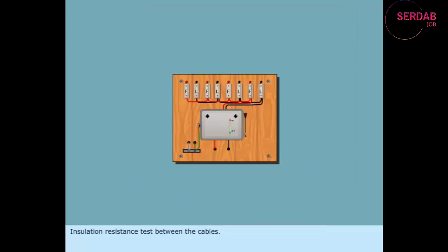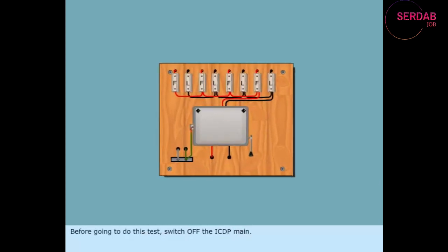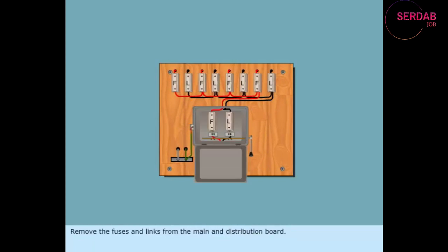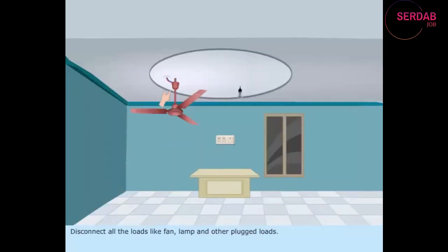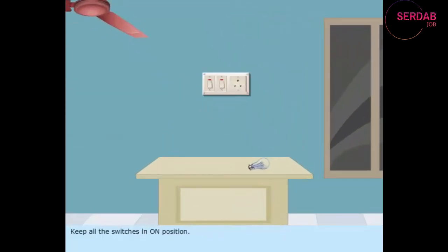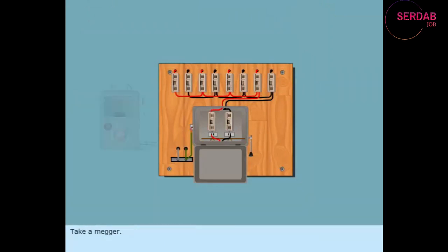Insulation resistance test between the cables. Before going to do this test, switch off the ICDP main. Remove the fuses and links from the main and distribution board. Disconnect all the loads like fan, lamp, and other plugged loads. Keep all the switches in on position. Take a megger.